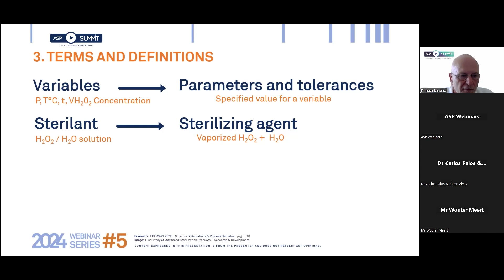Let's click again. The second keyword is sterilant. So the sterilant is the H2O2 H2O solution, which is contained in the cartridges. Usually it's a 59% H2O2 H2O solution. And when the sterilant is vaporized in the chamber of the sterilizer, it becomes a sterilizing agent. So the sterilizing agent is what is in contact with the surface of the medical device. You may want to keep in mind that the ISO definition of a sterilant differs from the one which is given to that term by FDA.